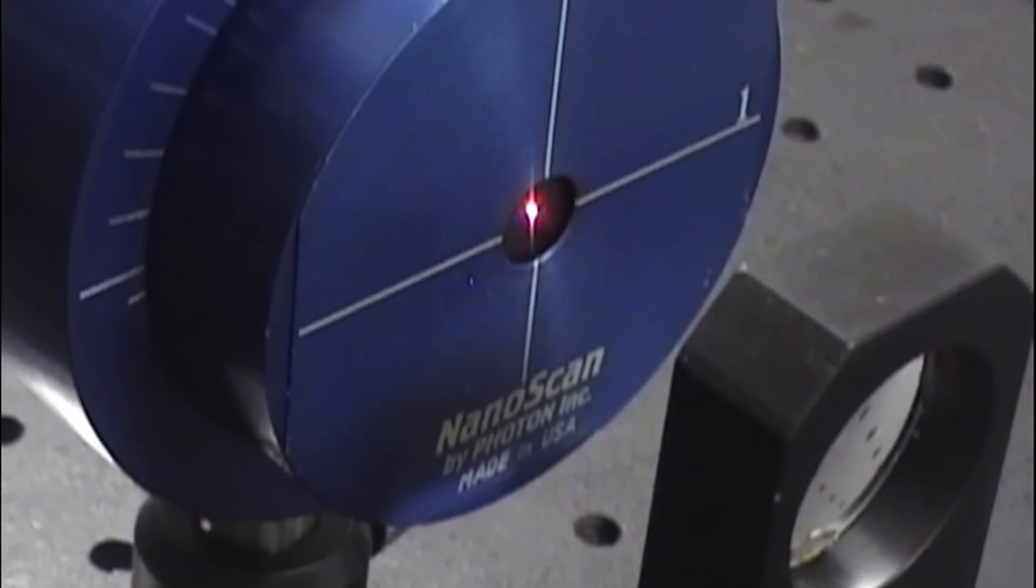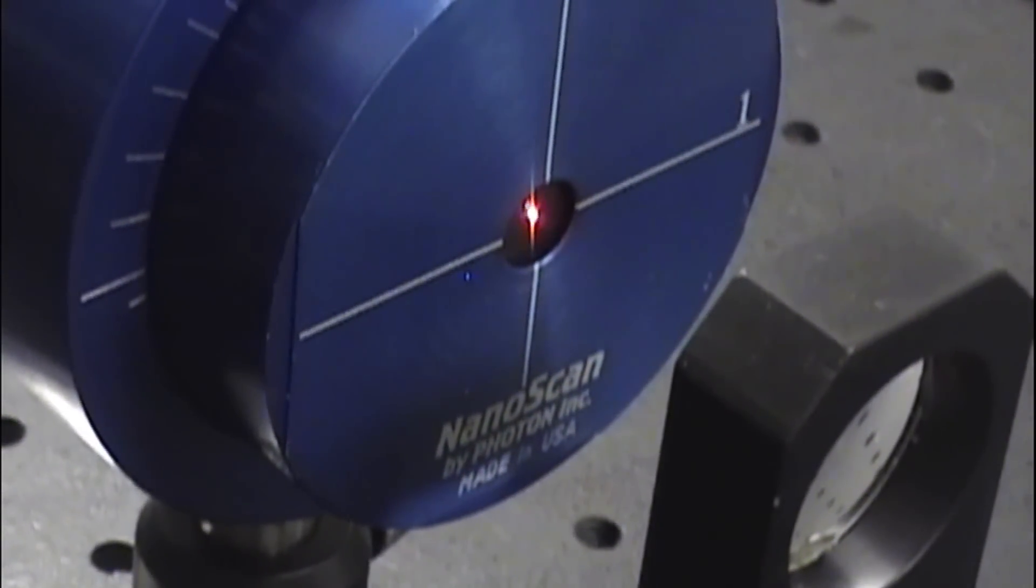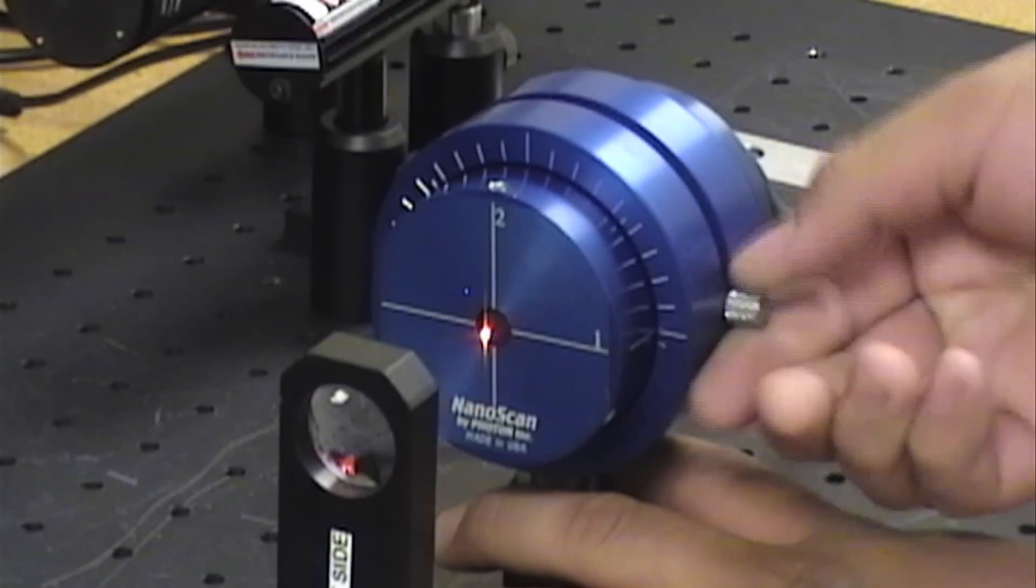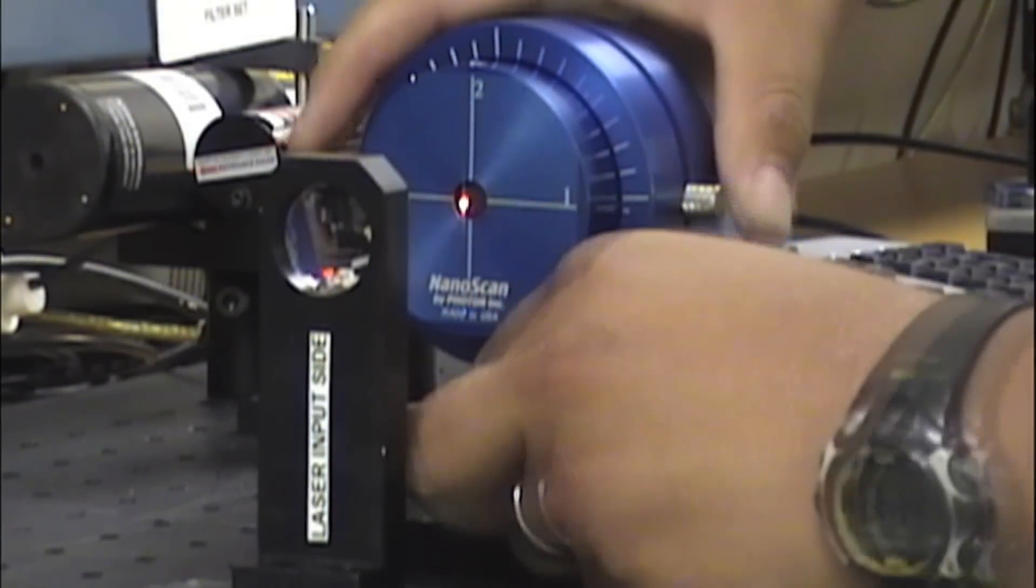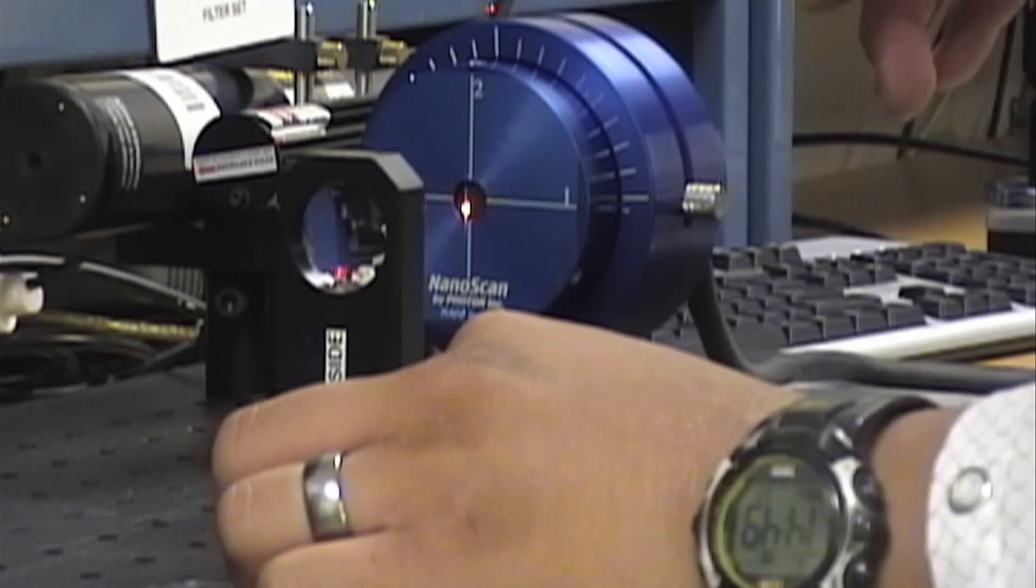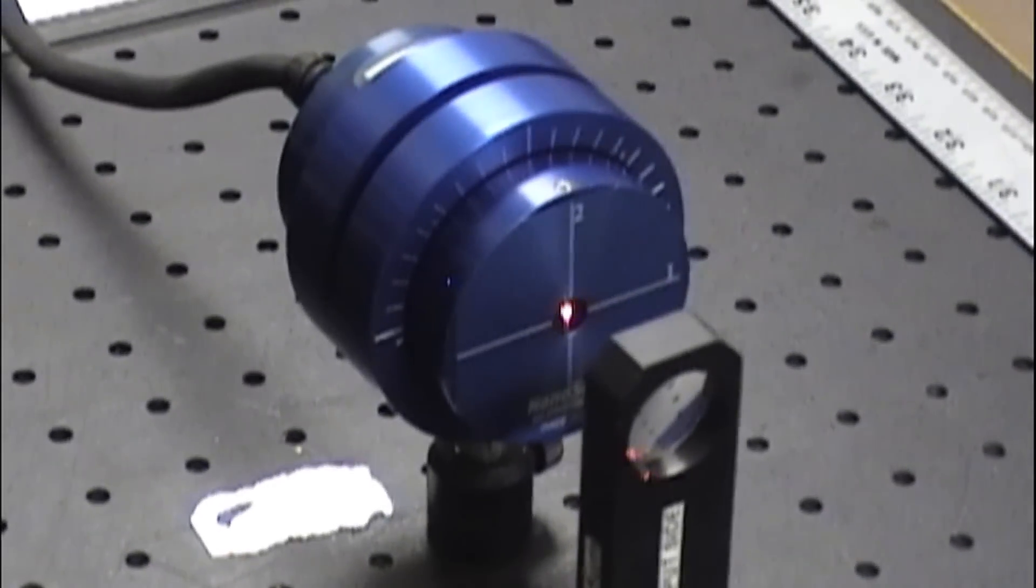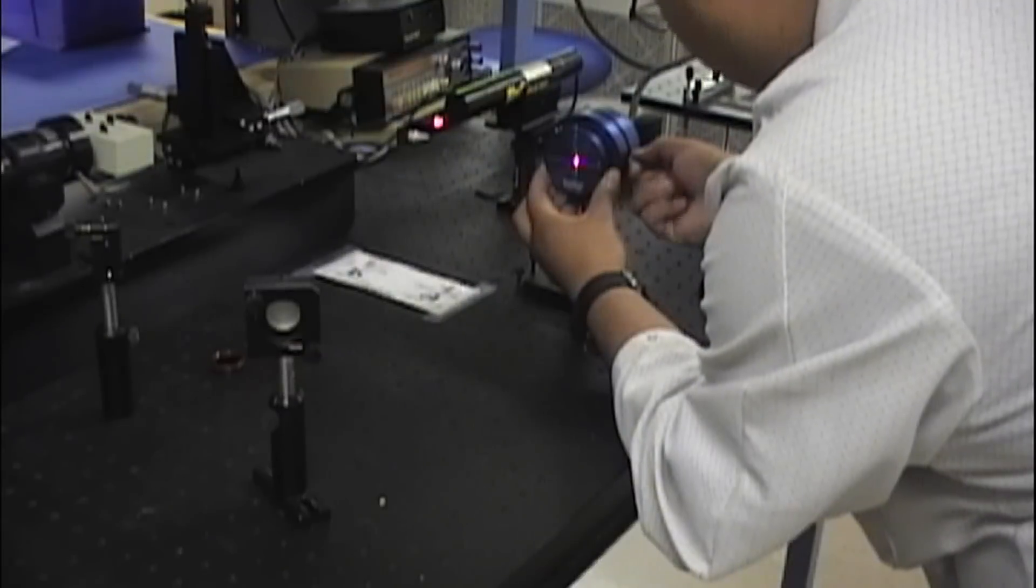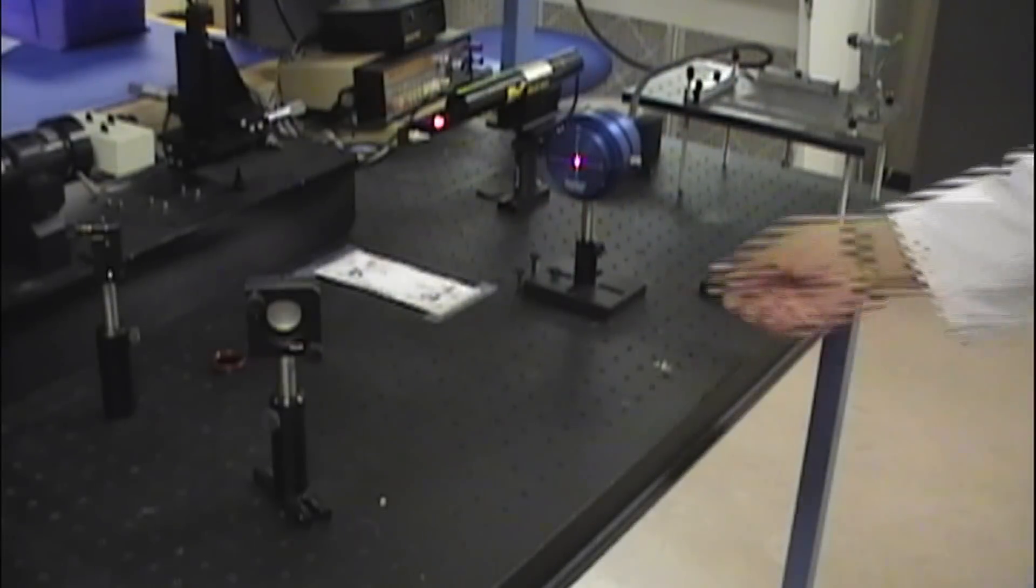When used with a proper laser optical setup, photon nanoscan profilers can be used for many years without repairs. If you have any reason to believe that a profiler is no longer performing within the original specifications, we recommend that you send it in for repair or recalibration by our trained technicians to bring the unit back to the proper NIST traceable standards.